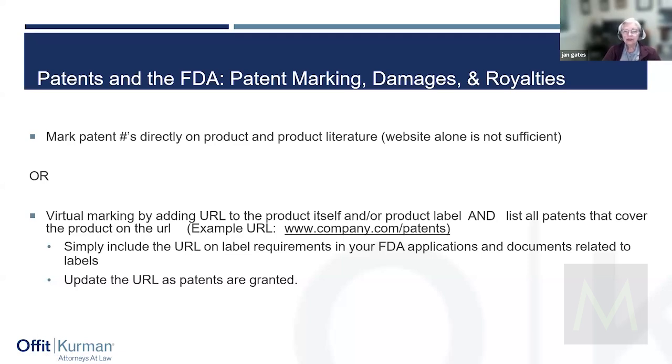No, I was just saying that labels are the major reason product gets recalled. So having the patent lawyer look at it before you actually put it on the market and submit it to the FDA is prudent, really, but Don had a good idea. Can you use a QR code in lieu of a URL? You'd have to ask the FDA because it could be mixed up with a 2D code that's required on the product. So I'm not clear how far you'd have to separate it out to make sure there wouldn't be an issue.